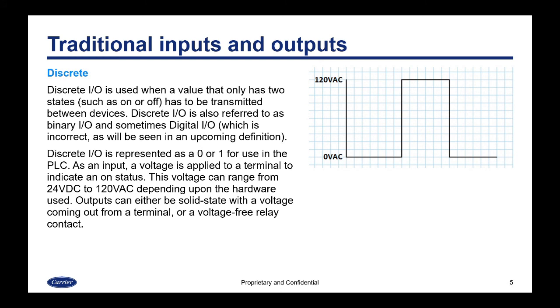Discrete I/O is used when a value that only has two states — such as on or off — has to be transmitted between devices. Discrete I/O is also referred to as binary I/O or sometimes digital I/O, which is actually an incorrect way to describe it. Discrete I/O is represented as a zero or one for use in the PLC. As an input, a voltage is applied to a terminal to indicate an on status. This voltage can range from 24 volts DC to 120 or even 230 volts DC depending on the hardware used. Outputs can either be solid state with a voltage coming out from a terminal, or a voltage-free relay contact.